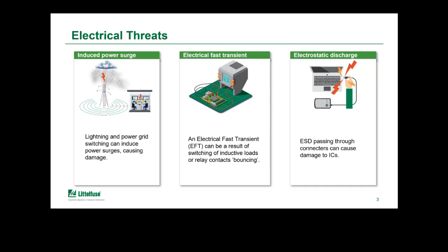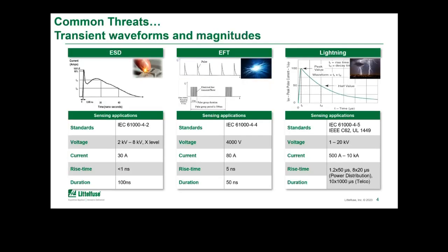discharge event. There are several standards out there that provide guidance as well as information on how to test or evaluate end equipment for these events and how best to simulate these atmospheric events. The first one, on the left-hand side here, is for an ESD event. For end equipment use, the most common standard is IEC 61000-4-2. It's the one that's most commonly referenced.